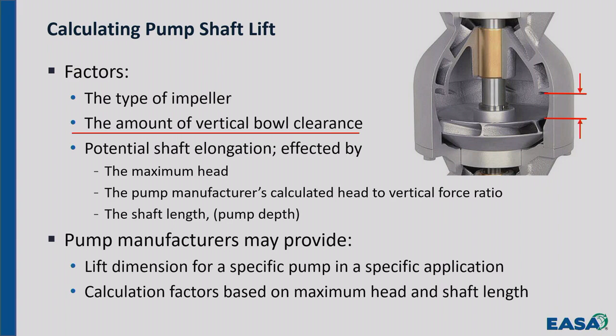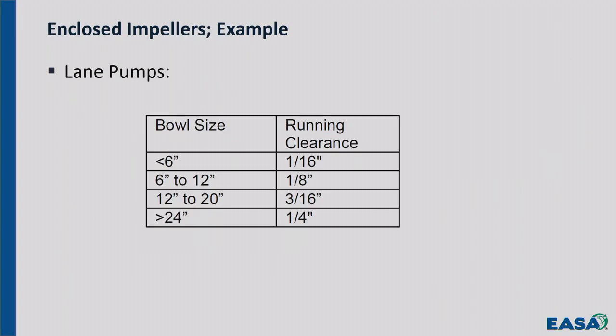If it's an enclosed impeller with a suction eye, you want to be someplace in between. If it's an open impeller, you've got a few thousandths of an inch underneath here. And to make that determination, you need that information from the pump manufacturer. Here are some numbers for Lane pumps for an enclosed impeller. They're not critical. So 1/16 of an inch, or 1/8, or 3/16 or 1/4, depending on the size of the pump. Those are nominal numbers, and you only have to get close to them because it's got a suction eye. Just don't want it rubbing.